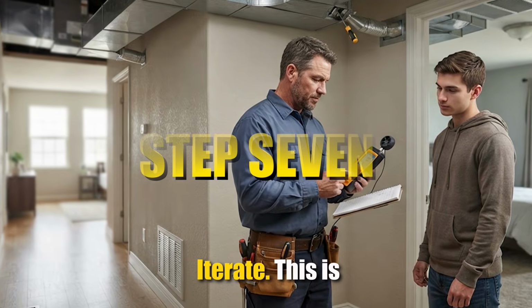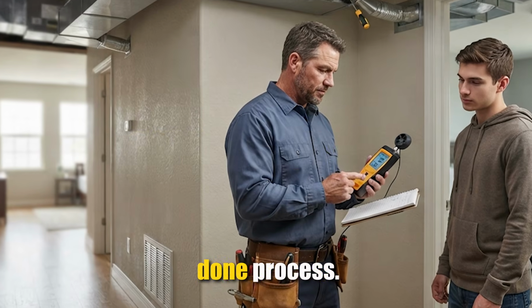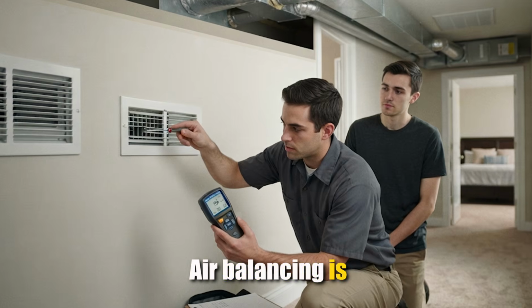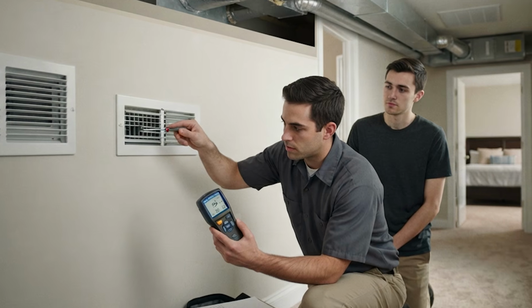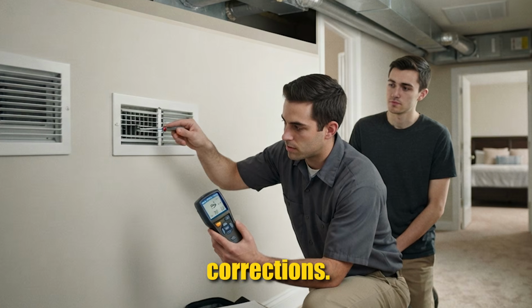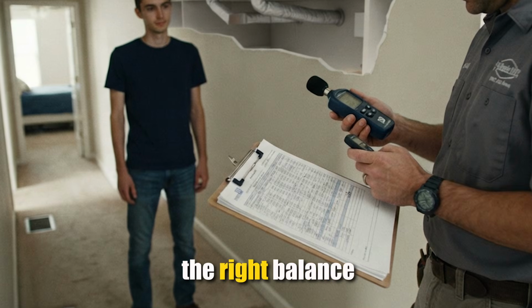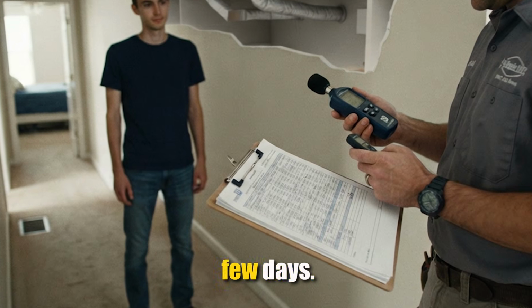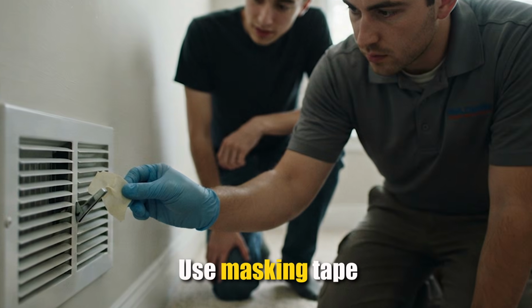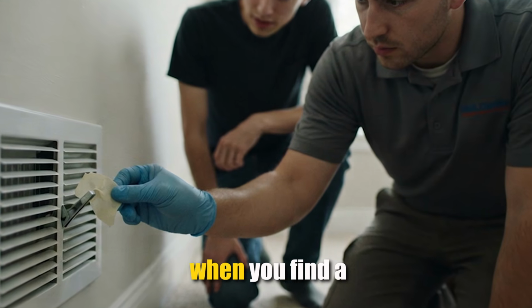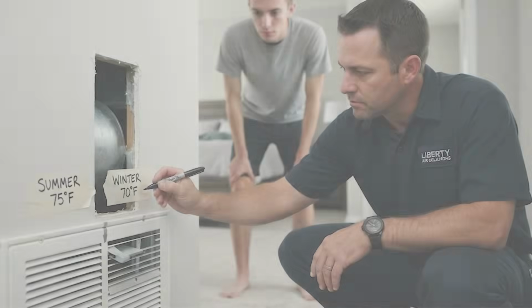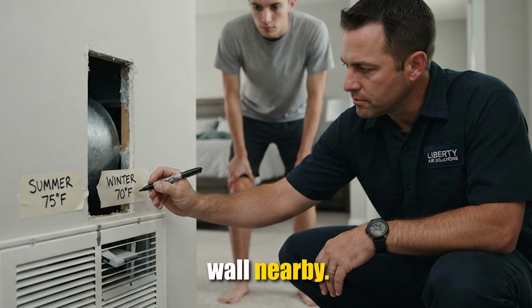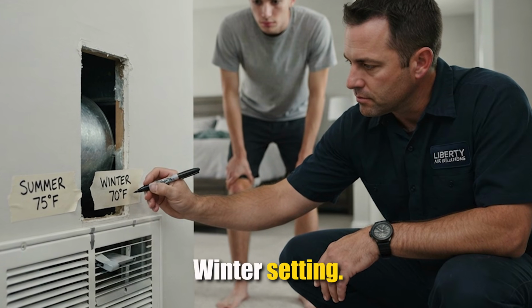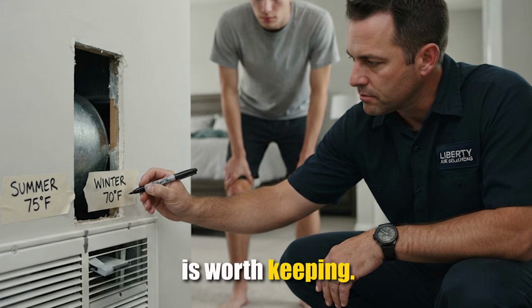Step 7. Iterate. This is not a one-and-done process. Air balancing is tuning. You make adjustments, wait, measure, make small corrections. Most people find the right balance in 2 to 3 sessions over a few days. Use masking tape to mark each damper position when you find a setting that works. Write directly on the duct or the wall nearby. Summer setting, winter setting. That information is worth keeping.